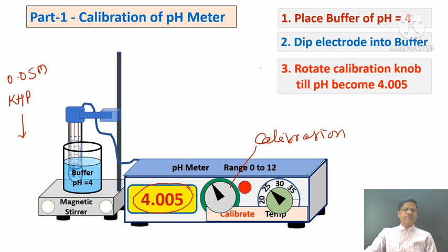Okay, so we have the buffer solution. Now the glass electrode must be washed with distilled water before dipping it into another solution. We must wash it out so that whatever potassium hydrogen phthalate is there is washed out. Otherwise, what will happen? It will give rise to error and contamination of the solution. Now remember very well. Once we have adjusted the temperature knob and the calibration knob, we have to fix them.